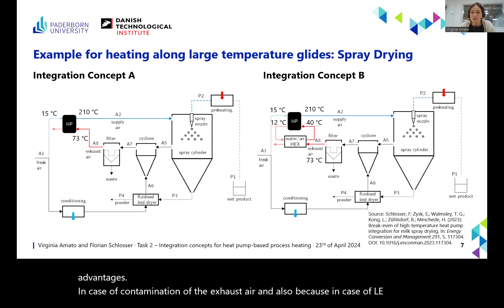There are several integration concepts possible. Here we show the simple concept in which the humid exhaust air is used directly as heat source, while in the second concept there is an intermediate cooling circuit. The advantage of using an intermediate circuit is that, although it is less efficient, it has advantages in case of contamination of the exhaust air, and also because in case of a leak we don't risk having the refrigerant going into the airflow.